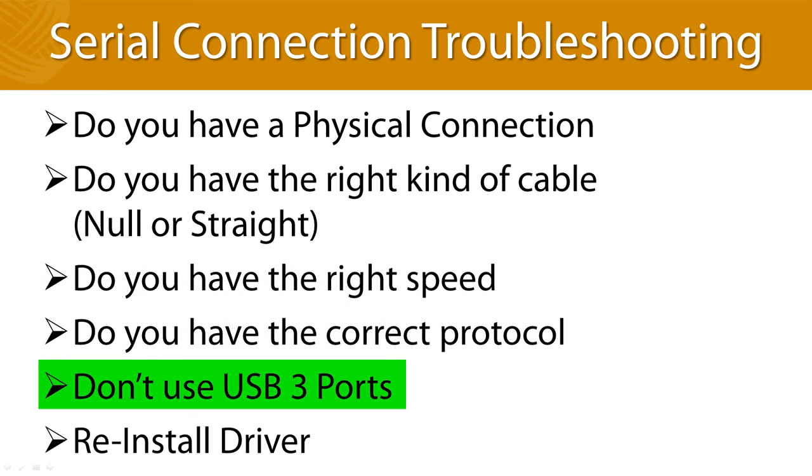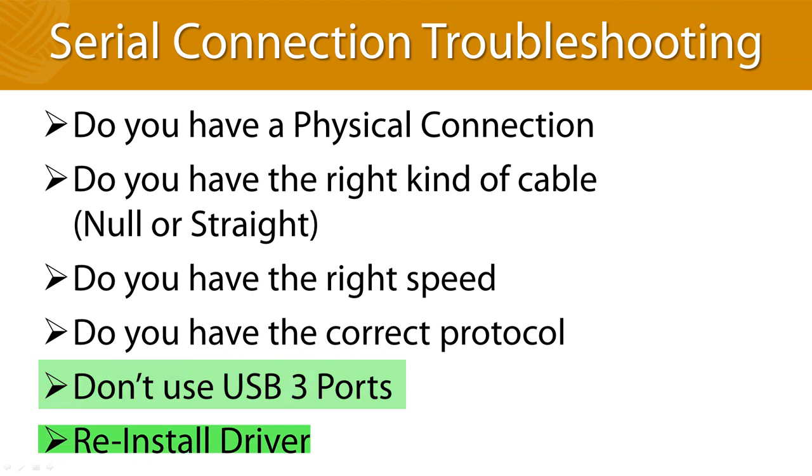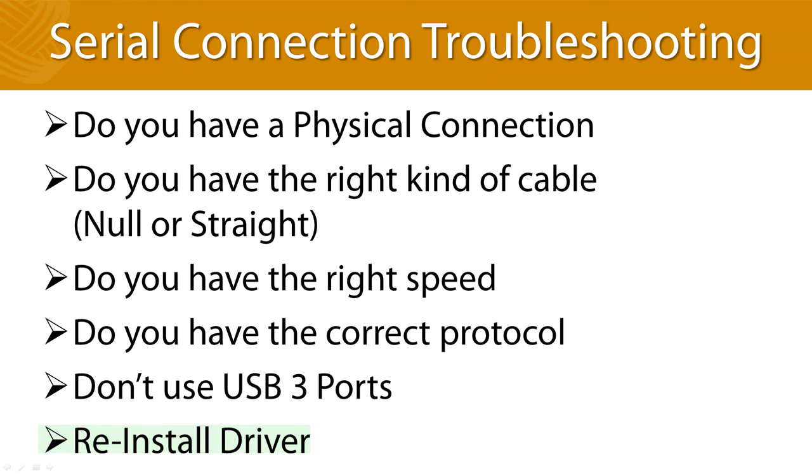I've had bad luck with USB 3 ports in the past. If you look at the physical USB port and it's blue, try another port that's not blue if you can. I've also had a couple of rare cases where something happened to the USB to serial converter driver, and communication to SEL relays was normal, but GE UR relay communication was painfully slow. I uninstalled and reinstalled the driver, and suddenly everything was fine.